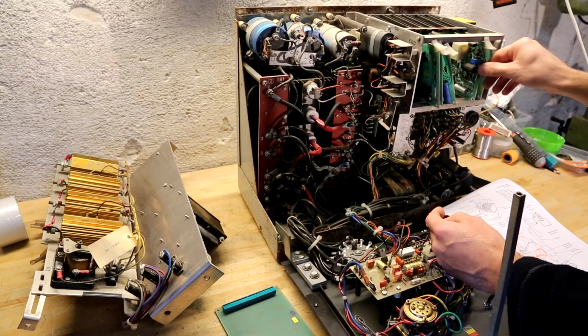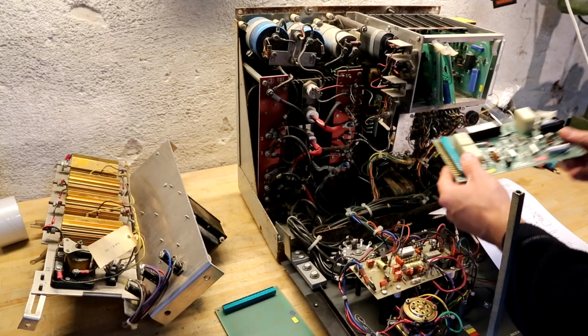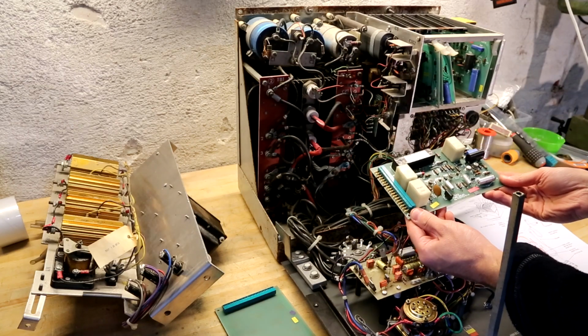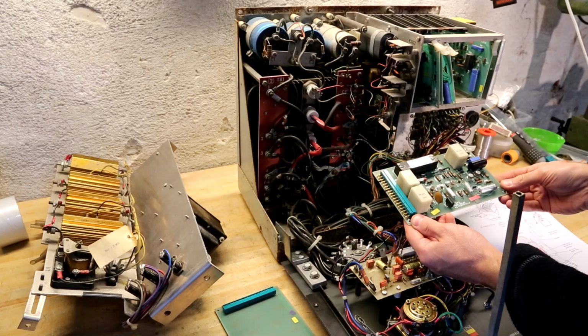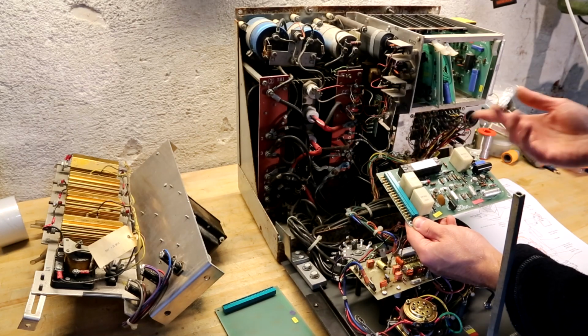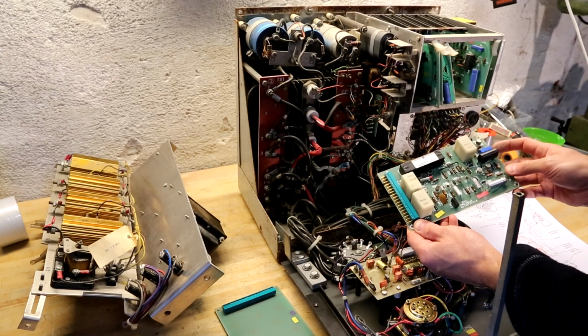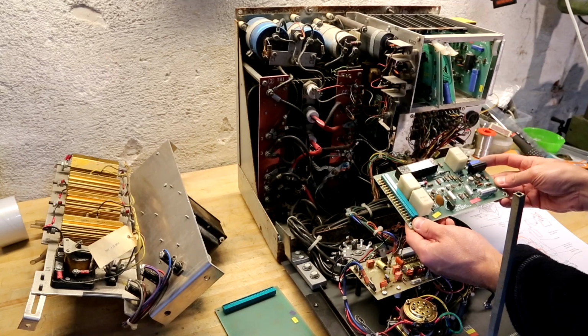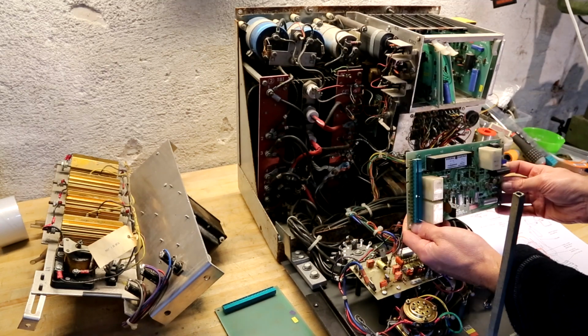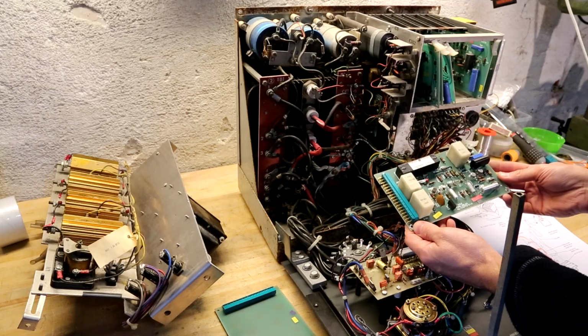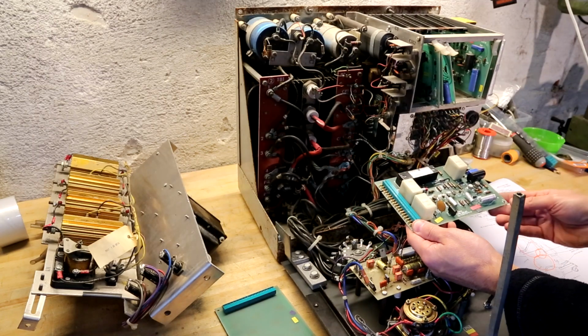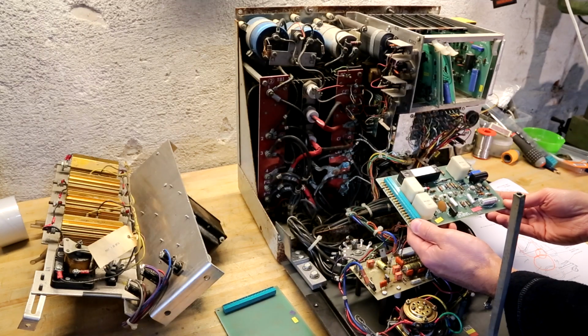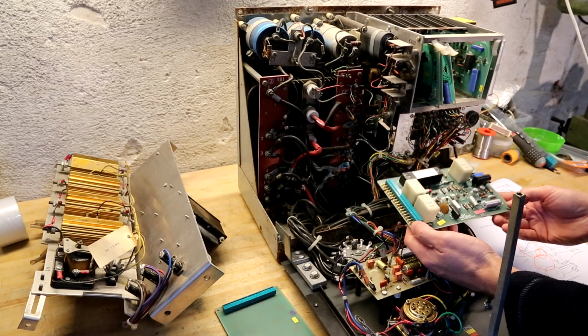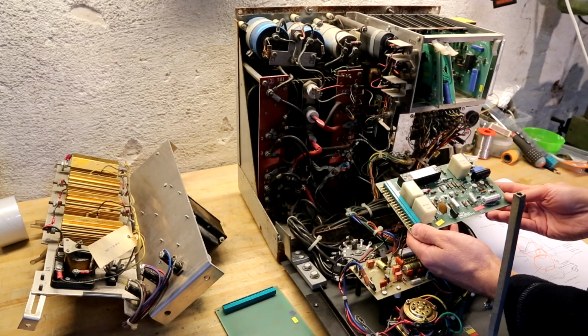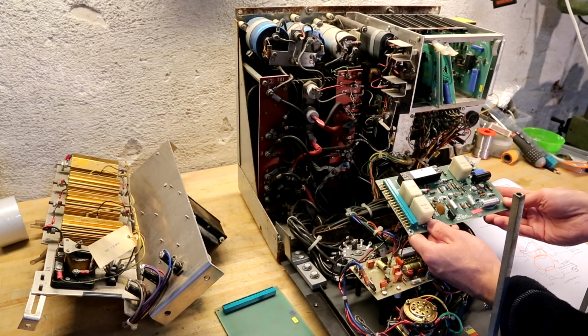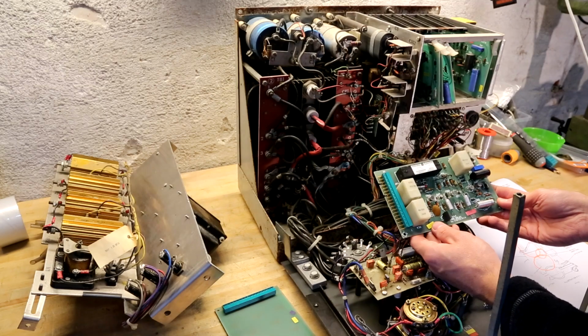And card 4 here, this is the time delay board. So that is generally 4 relays and then 4 timing circuits. Just a single pot meter here, so only one of them is adjustable. So this is probably timing of the X-ray exposure and such. These are generally something that you would have a lot of safeguards on and surveillance. So you don't overexpose a patient and such?